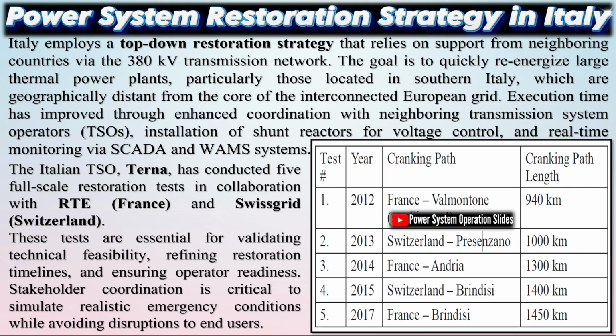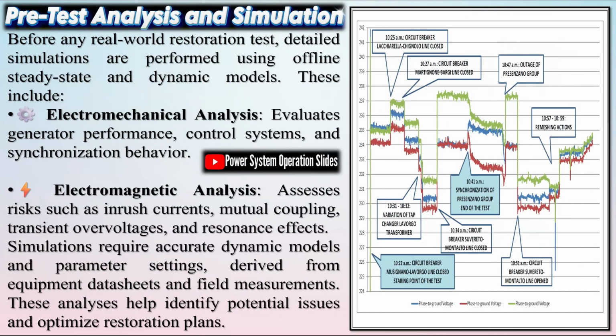This rapid execution was enabled by a pre-compensated transmission path, segmented into 4 to 5 coordinated sections, each containing multiple substations and transmission lines energized sequentially. Measurement data confirmed that electrical transients matched predictions from offline simulations. The protection and control systems performed reliably throughout the test, validating both the technical design and operational readiness. Voltage recordings from Musignano, the first Italian substation on the path, aligned with expected phase-to-ground profiles, further confirming the test's success.